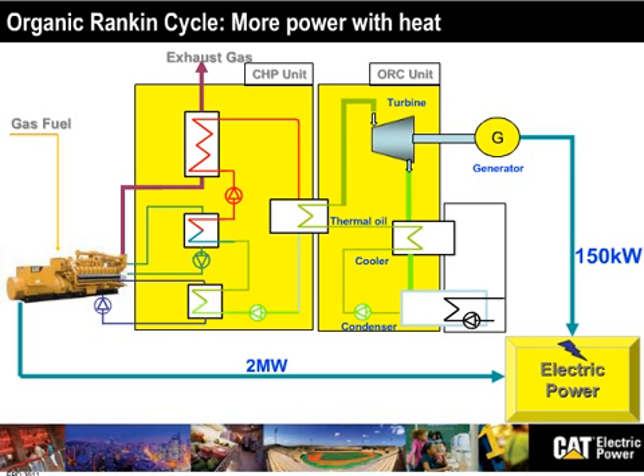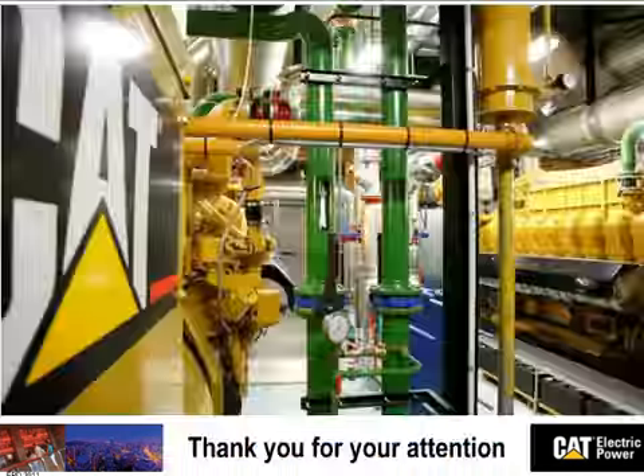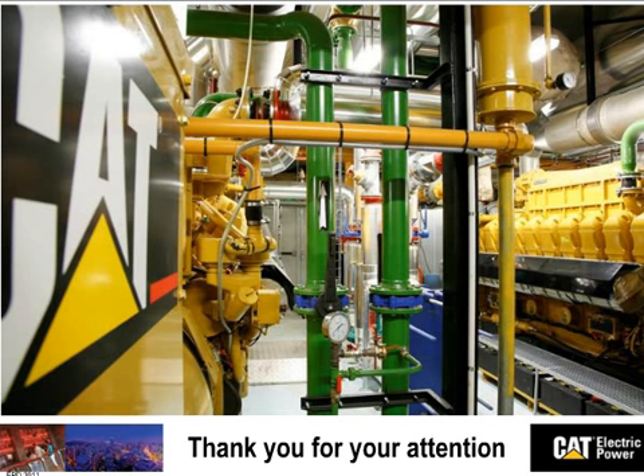Thank you, Francois. Another question coming in from Vince DeMarco with Washington Gas Energy. What is the typical installed cost per kilowatt for engines in the 2 to 5 electrical megawatt range for operation on natural gas? With what type of heat recovery? I'll think hot water, for instance. Let's pick hot water. I would say $800 per kilowatt. I think that's a good number. Okay. That includes the genset plus the heat recovery system.